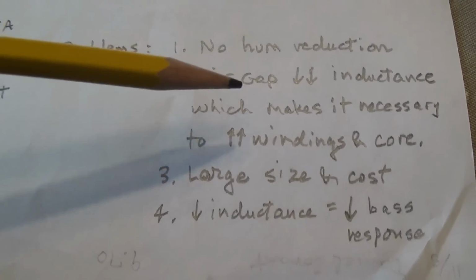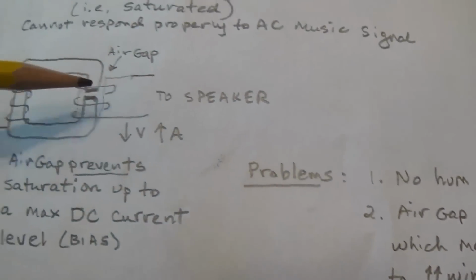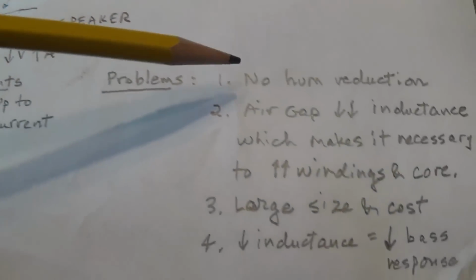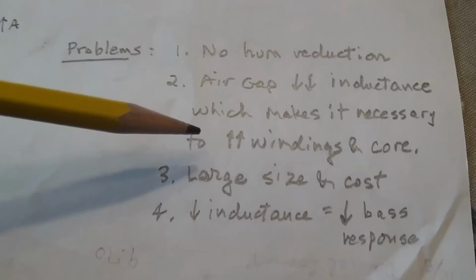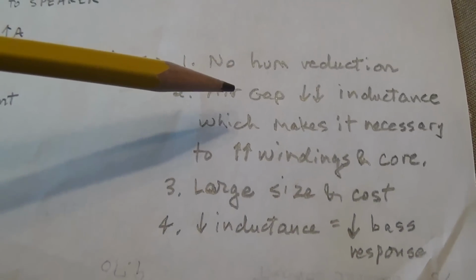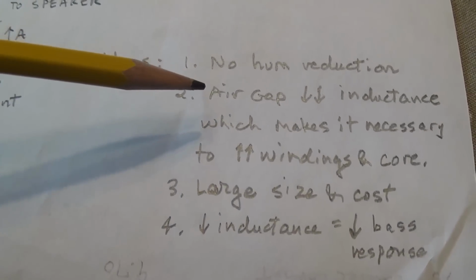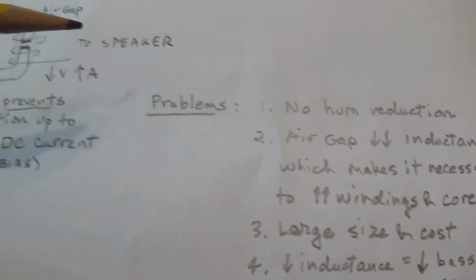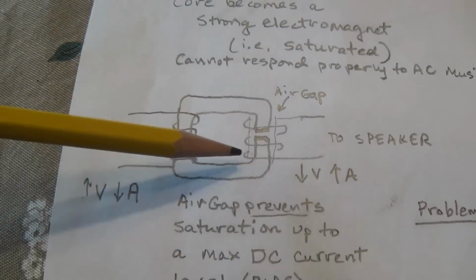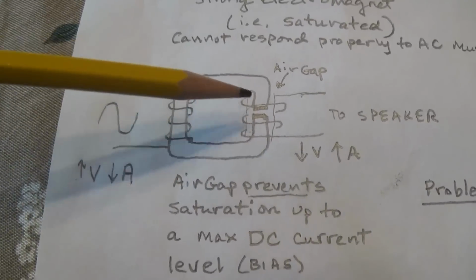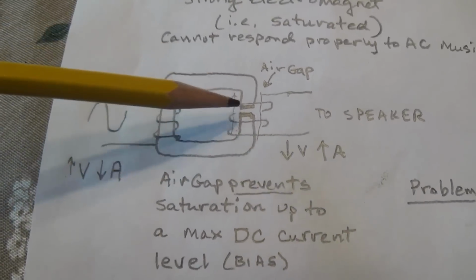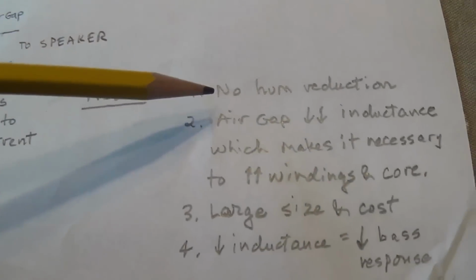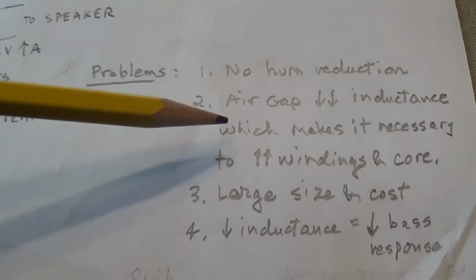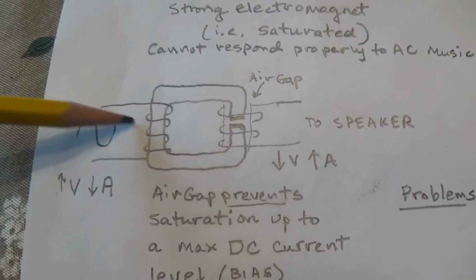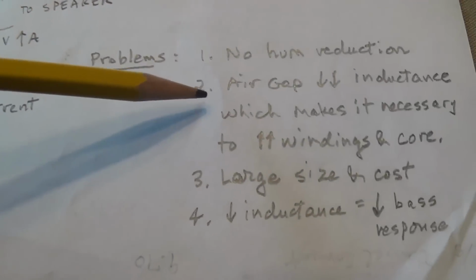Now here's a real issue. The air gap that we put here greatly reduces the inductance of the transformer. In other words, it sort of fights against what output transformers do. As the inductance goes way down, it does not tend to do its job properly.